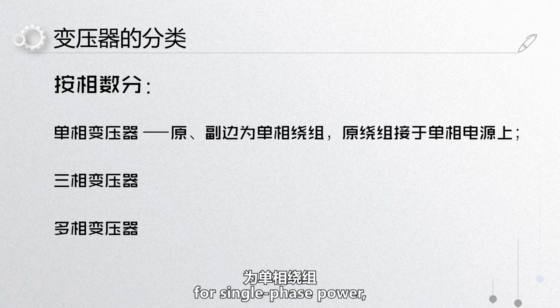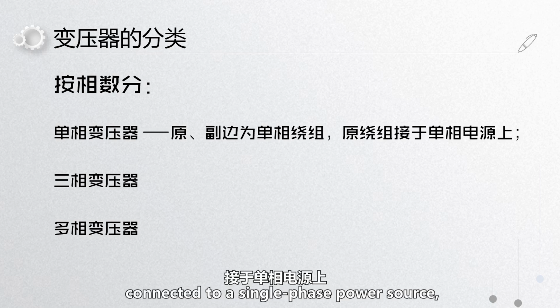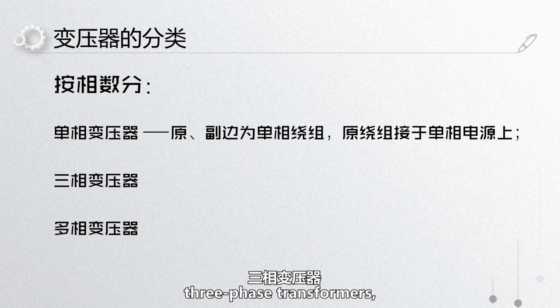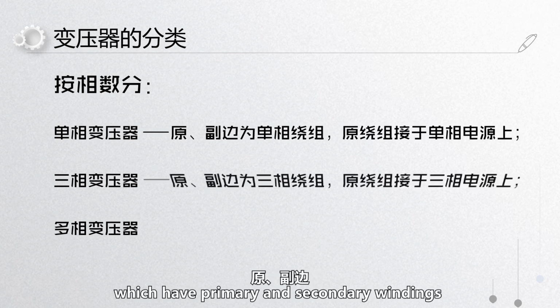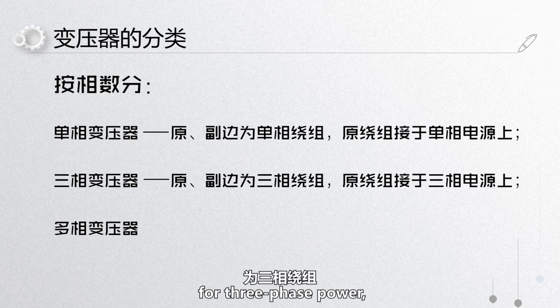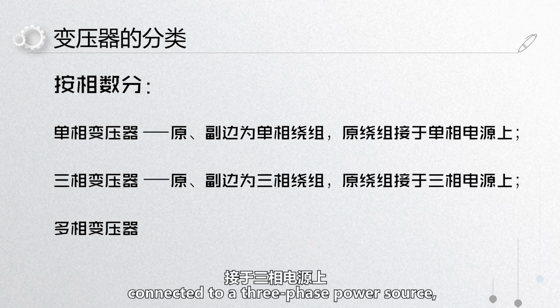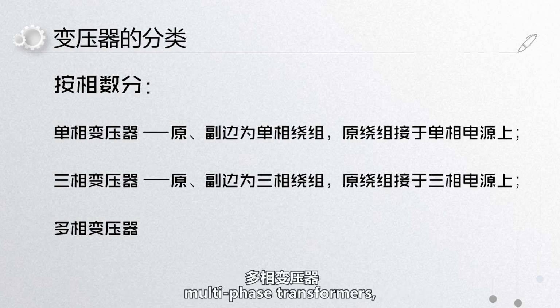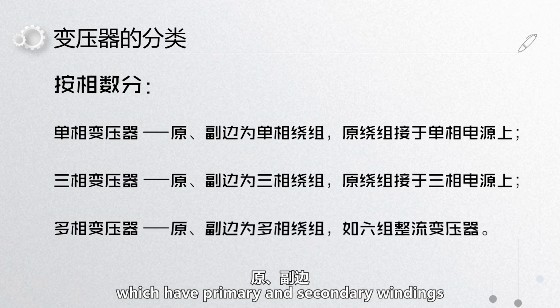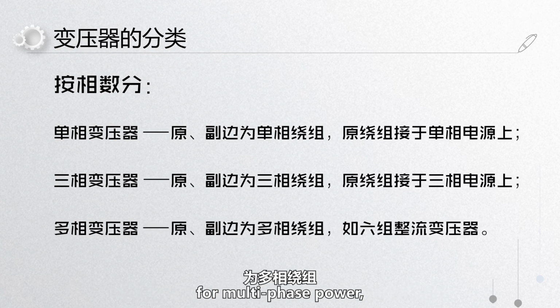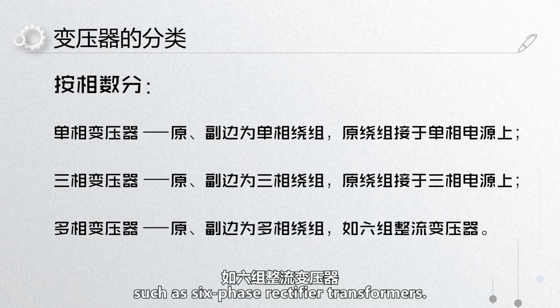According to the number of phases, transformers can be classified into single-phase transformers, which have primary and secondary windings for single-phase power, with the primary winding connected to a single-phase power source. Three-phase transformers, which have primary and secondary windings for three-phase power, with the primary winding connected to a three-phase power source. Multi-phase transformers, which have primary and secondary windings for multi-phase power, such as six-phase rectifier transformers.